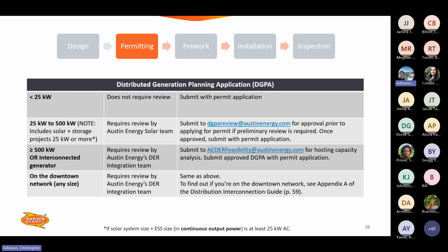Greater than 500 kW or interconnected generator requires review by the DER integration team. You're going to see the engineers. Submit to AE/DER feasibility at austinenergy.com for hosting capacity analysis and any other inquiries. Submit approved DGPA with the permit application. If you are on the downtown network, requires review by Austin Energy's DER team, same as above. To find out if you're on the downtown network, look in the DIG, the interconnection guide on page 59. There is a map of what constitutes as the downtown network.